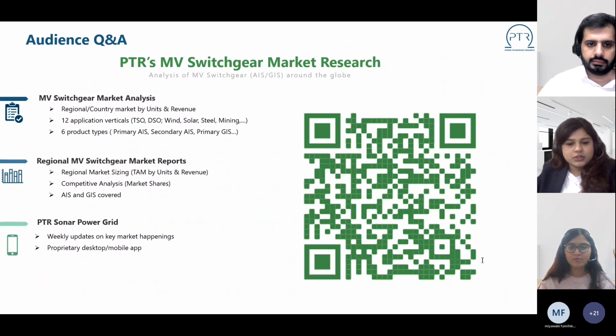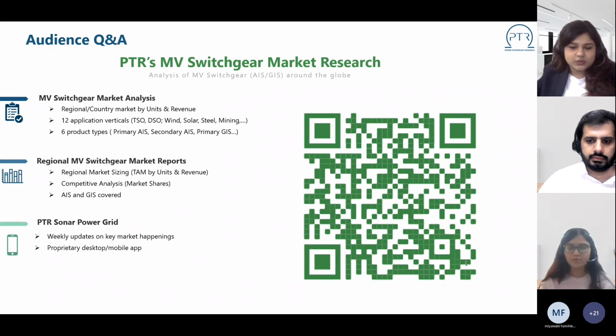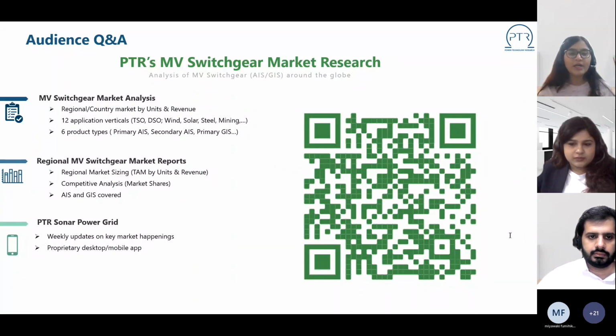The next question is, what is the future of solid dielectric switchgear? Solid dielectric is currently available in the market as an insulation media and alternative to SF6. It is considered a solution to many problems, because even with AIS instead of SF6-based GIS, although SF6 isn't used as a gas in the compartment for bus bar insulation, it is still used in disconnecting switches, circuit breakers, or as an arc extinguishing medium within the equipment in one way or another. So solid dielectric switchgear, which is completely free from the use of SF6, can help address environmental issues.